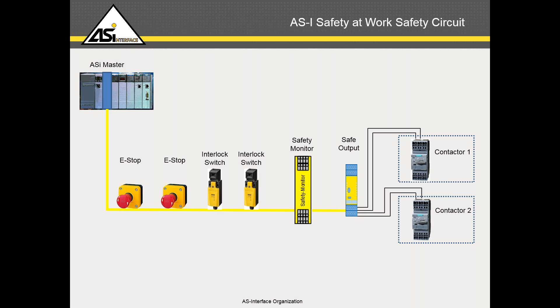In some of the studies we've done as a group, when we look at the cost analysis of the safety at work system and installing AS-i to it, you see with a small system with a couple I/O points or safety points, in the conventional system your component cost is a large portion of cost, and installation is about 20% of that. By going with the AS-i system, your component cost will increase a little bit, since we're selling more intelligent equipment, but the big benefit is seeing the installation cost go down dramatically. In this small machine case, we're estimating anywhere between 5% savings in total cost of the system.